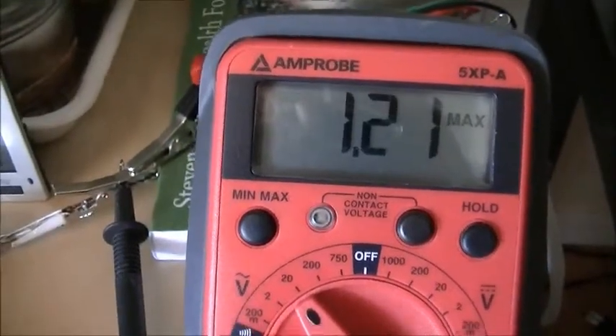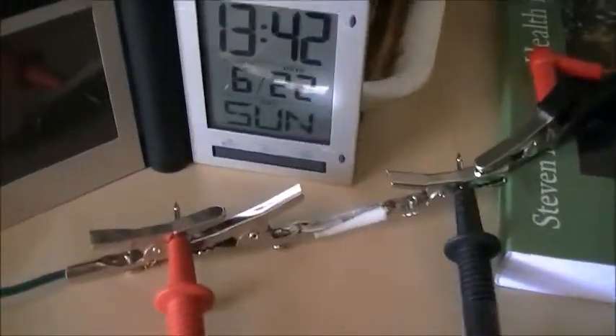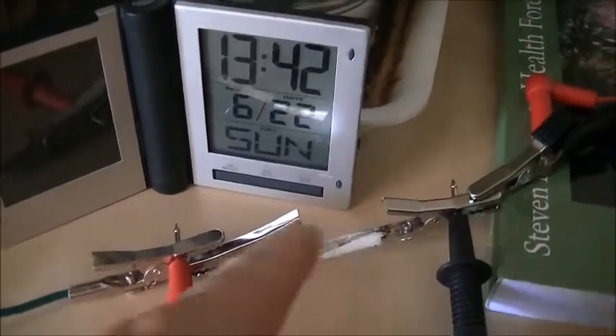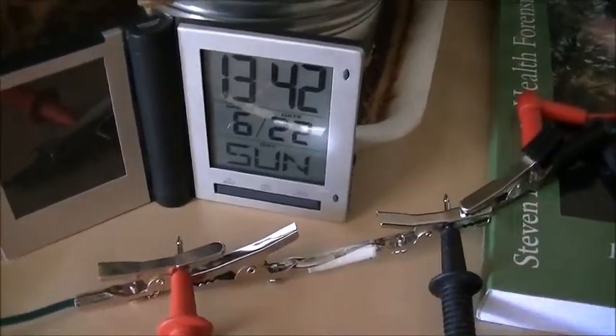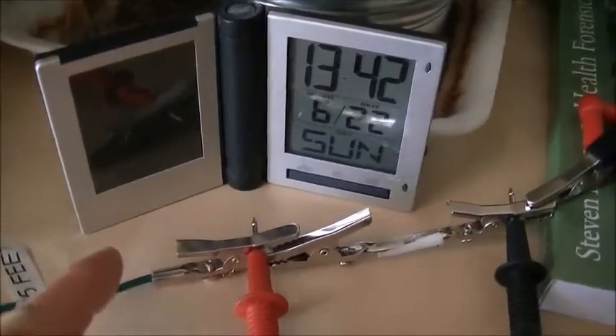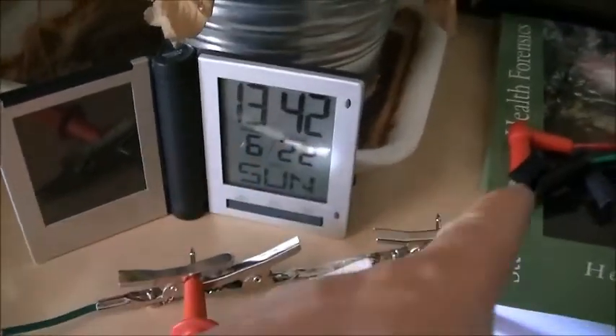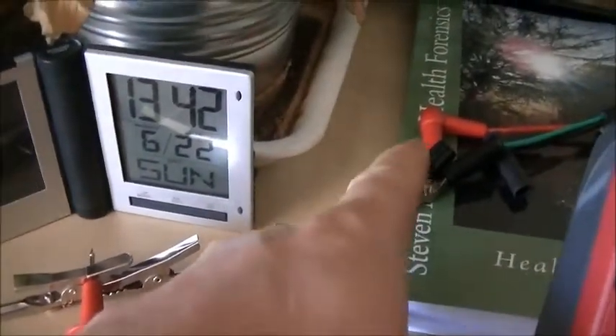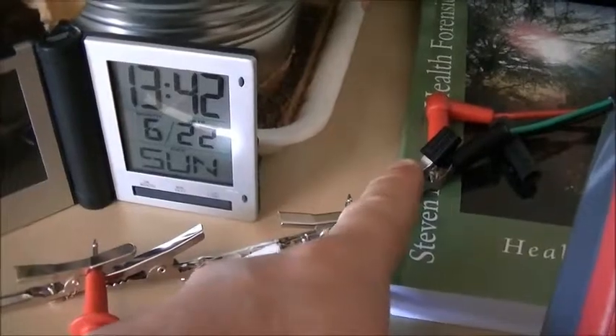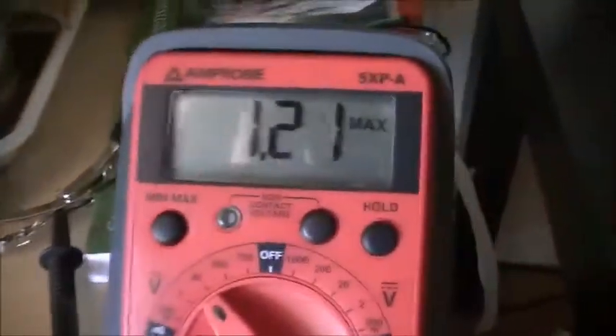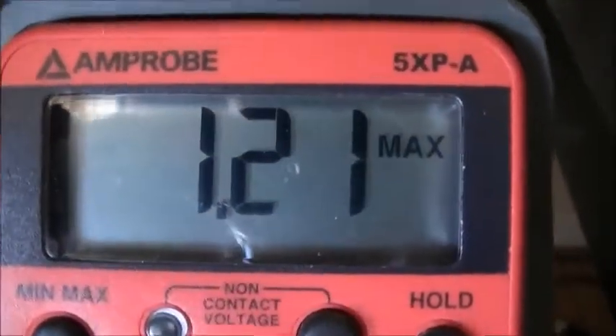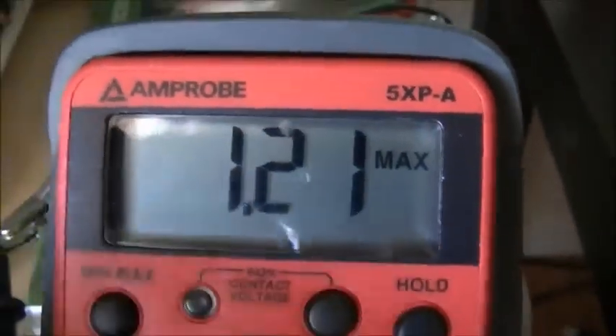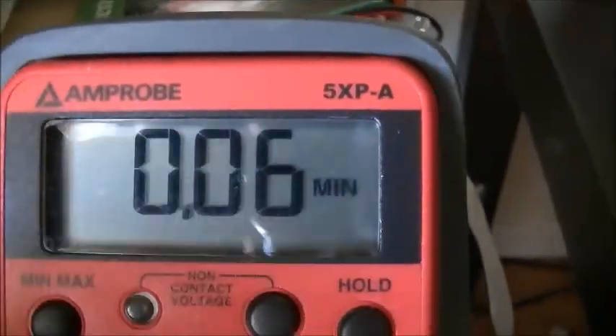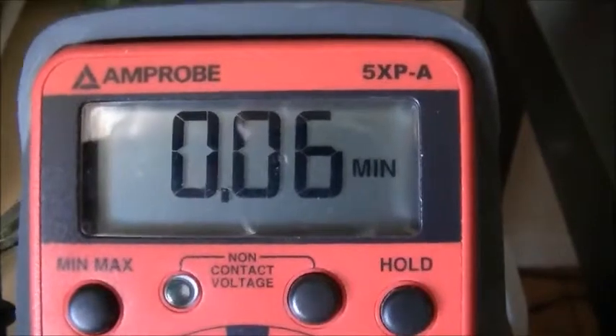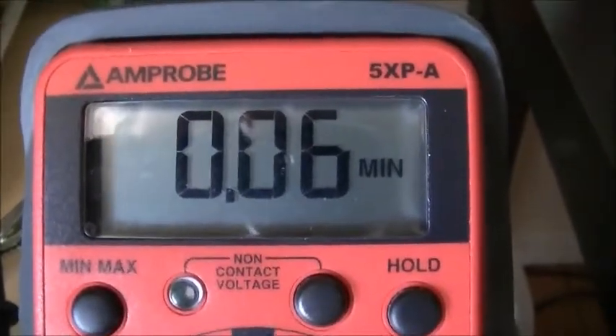This meter has now been logging overnight with the 500 ohm resistor across the probes. On the left, we have the non-electrified ground rod, and on the right, the electrical utility grounding system of the home. This was the overnight value: 1.21 maximum AC volts, and the overnight minimum was 0.06.